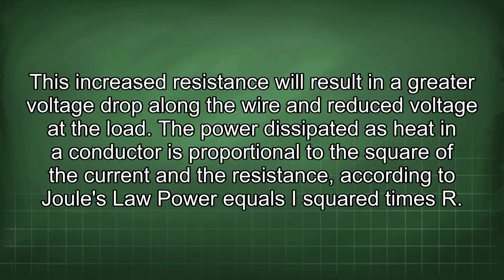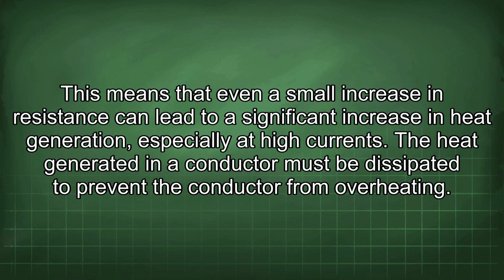The power dissipated as heat in a conductor is proportional to the square of the current and the resistance according to Joule's law. Power equals I squared times R. This means that even a small increase in resistance can lead to a significant increase in heat generation, especially at high currents. The heat generated in a conductor must be dissipated to prevent the conductor from overheating.